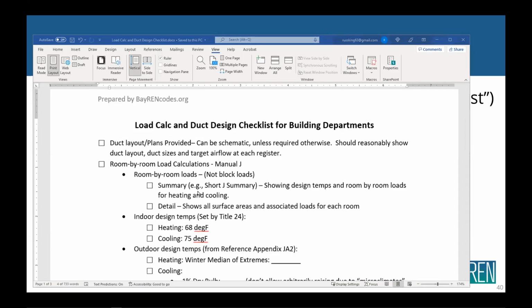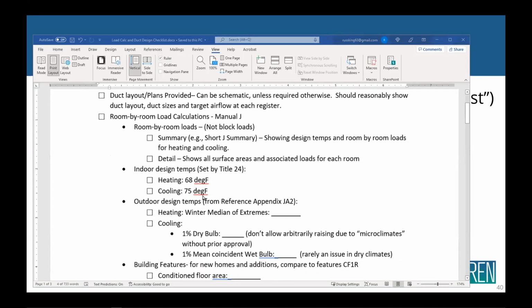will have certain forms that are printed out. So you want to ask for those. It'll show each room, it'll show the load at each room. You want to check the design temperatures, make sure those are consistent with what your code says. In California, it's 68 for heating and 75. For most of the country, it's actually 70 for heating and 75 for cooling. These are the indoor temperatures. These are essentially what you're setting your thermostat to.